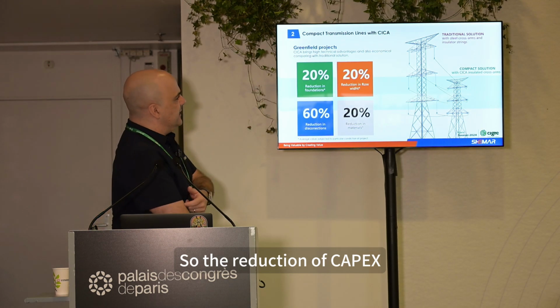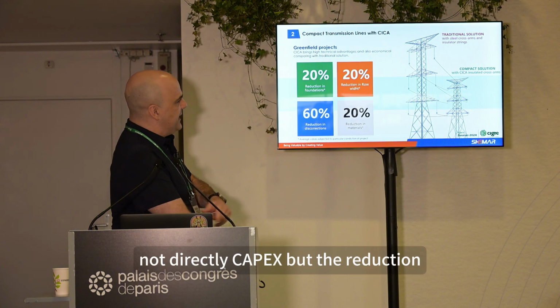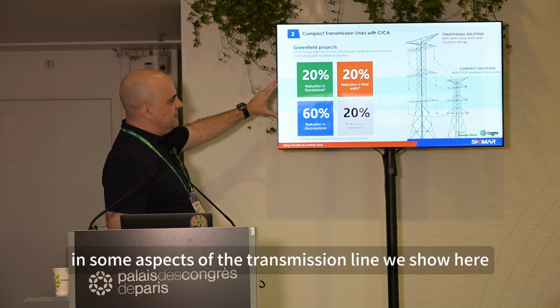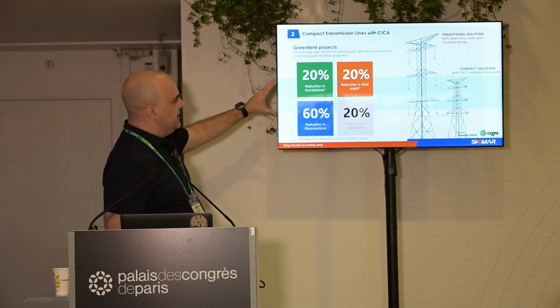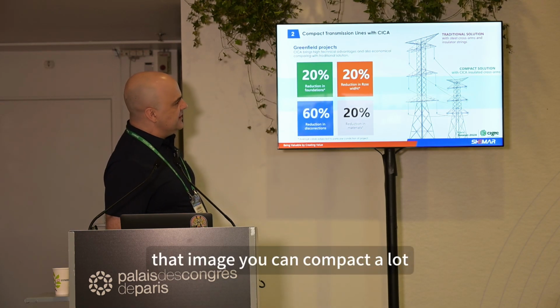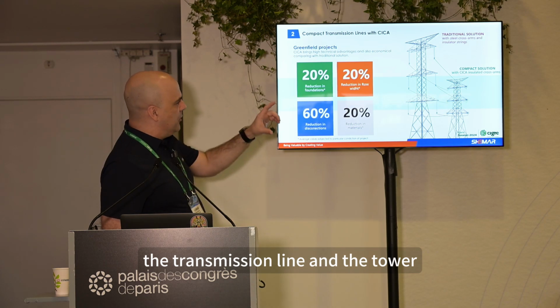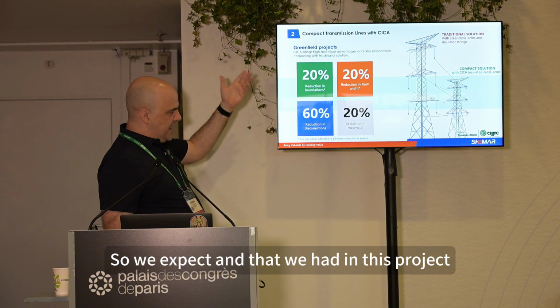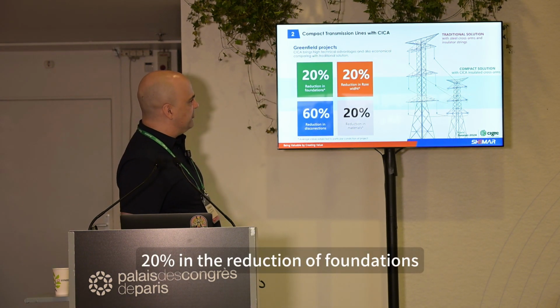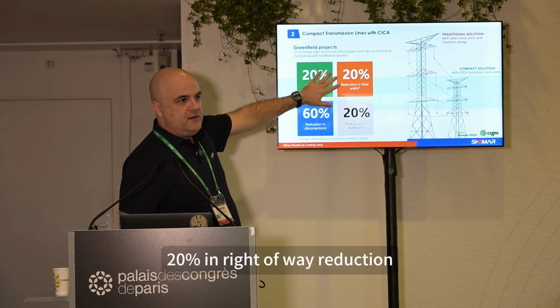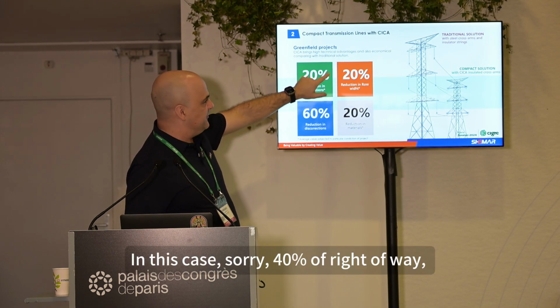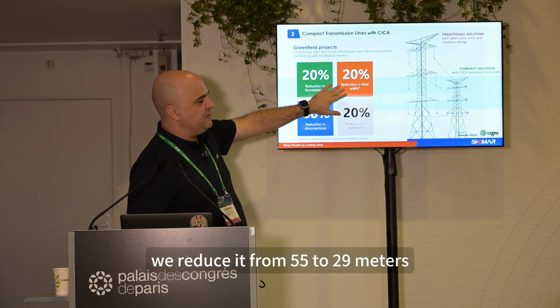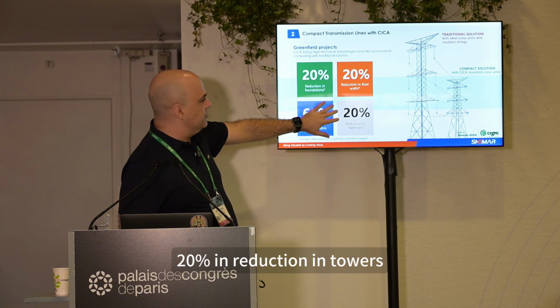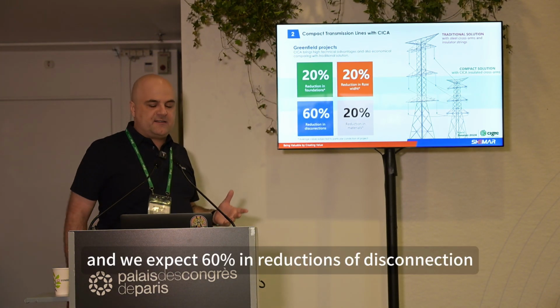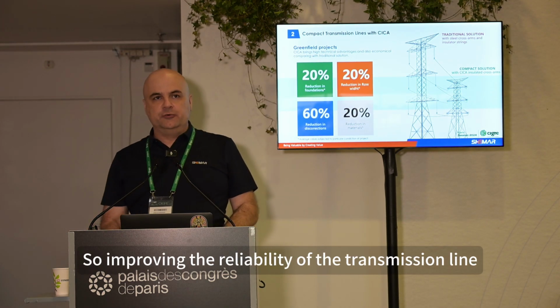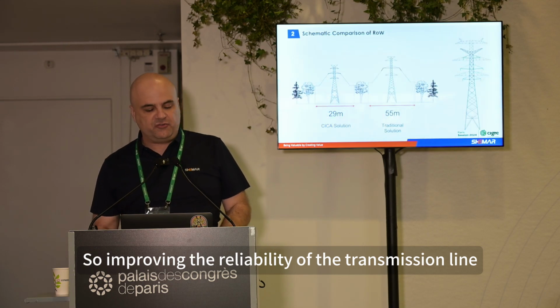So regarding the reduction of capex, not directly capex, but the reduction in some aspects of the transmission line shown here: using CICA you can compact a lot the transmission line and the tower. We expect, and achieved in this project, 20% reduction in foundations, 20% reduction in right-of-way -- in this case we reduced right-of-way from 55 to 29 meters, about 40% -- 20% reduction in towers, and we expect 60% reduction in disconnections, improving the reliability of the transmission line.